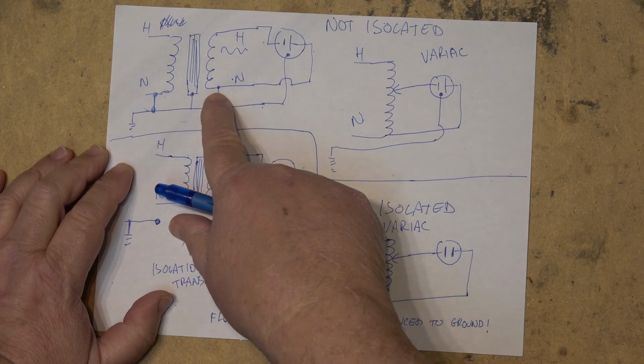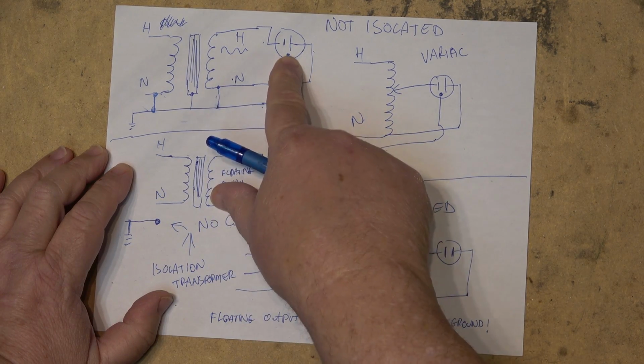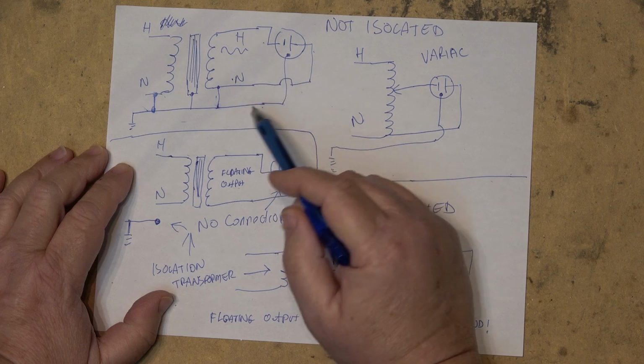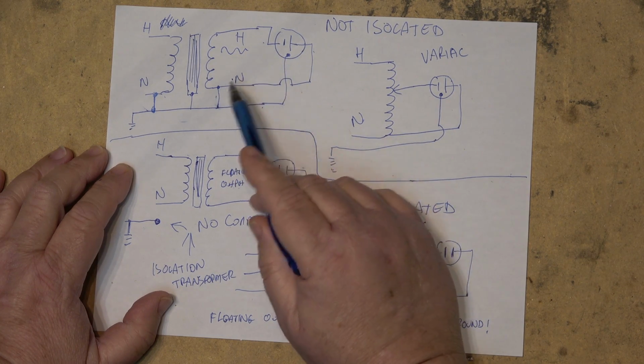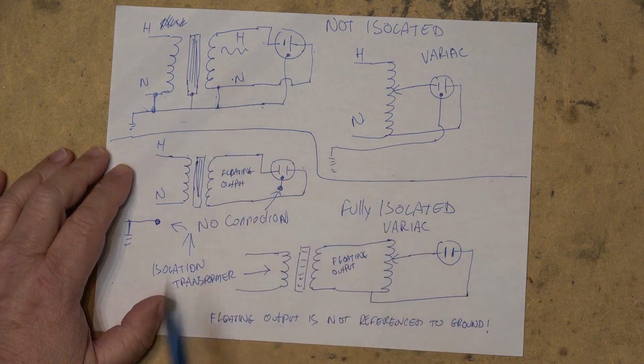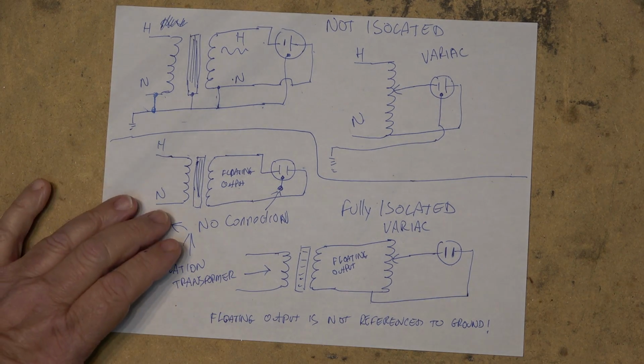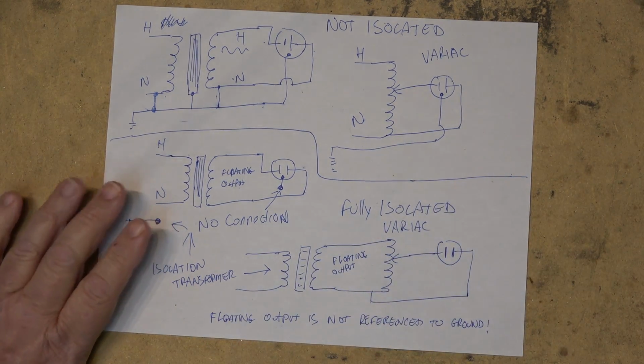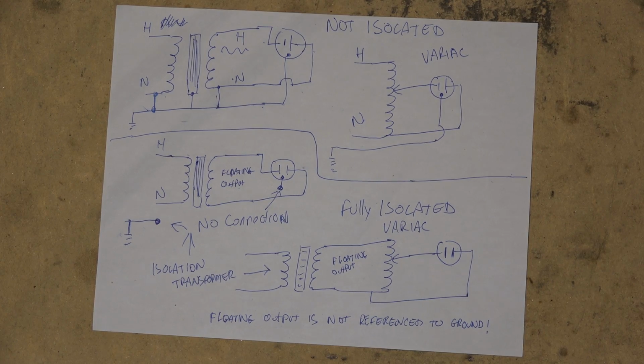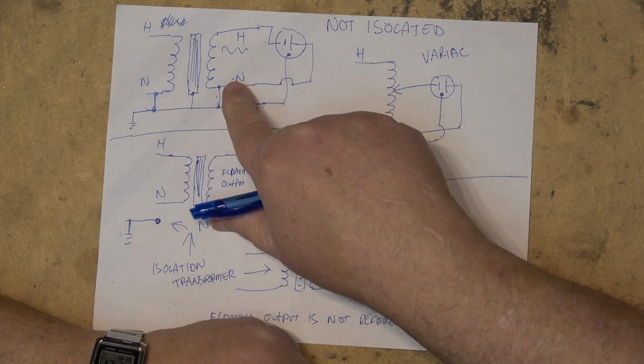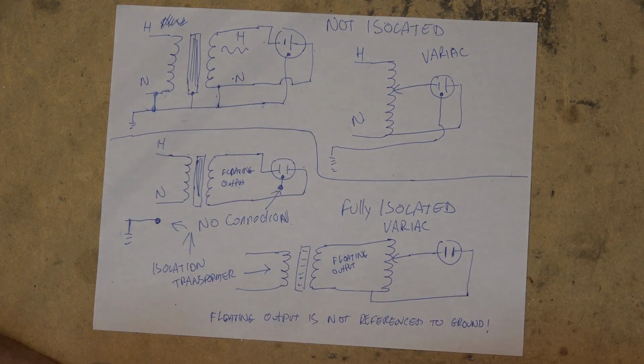You don't want this one, and you definitely do not want a ground wire going through. That is not how isolation transformers operate, because you've removed that safety factor of having a completely isolated output. And unfortunately, most of the transformers that you will buy are like this. In fact, to get UL certification, they probably have to be like that, because somewhere in the code they're going to say your outlet has to be grounded, and that is not what you want for a safety isolation transformer.